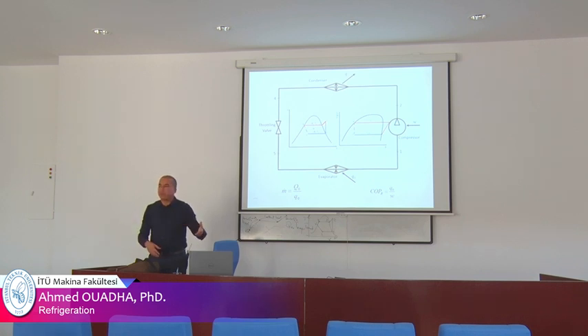We need, for example, to cool drinks. Here in this room, we have bottles of drinks. We need a temperature of evaporation about zero because drinks are conserved at about 6 degrees. To freeze meat, we need a negative temperature, for example minus 15 or minus 20. Is it clear? The second parameter, T condensation.